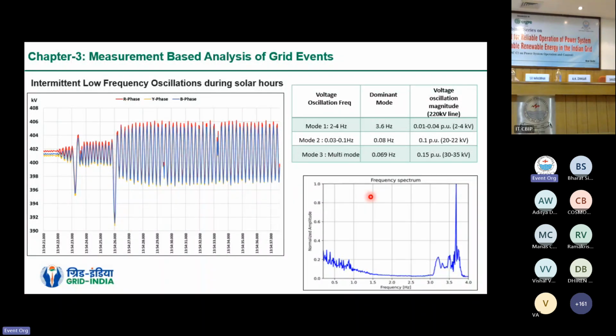Chapter 3 of the report also details the measurement-based analysis of grid events. In that, we are witnessing some issues with small signal stability within the RE pockets, and we are observing low frequency oscillations. We were able to capture the low frequency oscillations based on the phasor measurement unit data, which provides us output at every 40 milliseconds. Such high resolution data helps us in capturing low frequency oscillations.